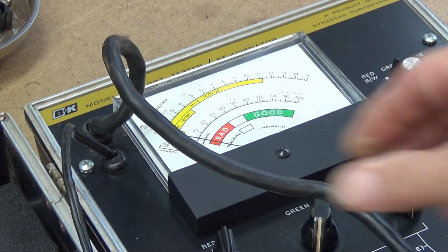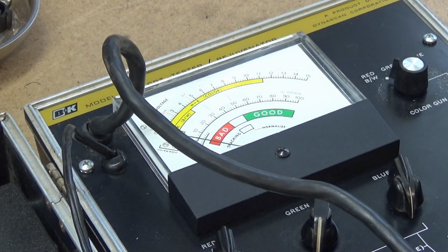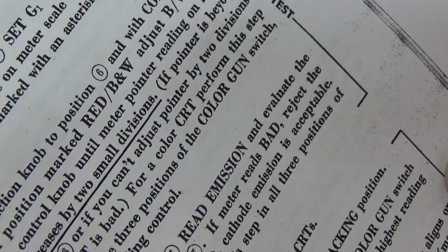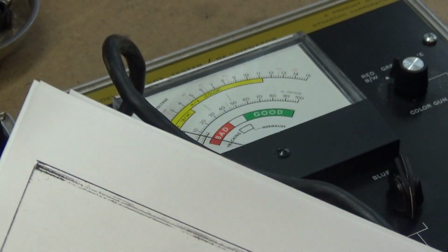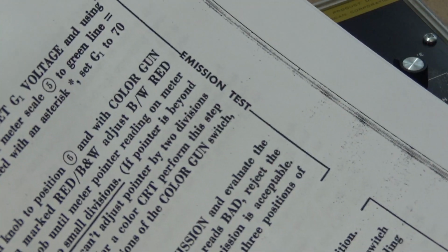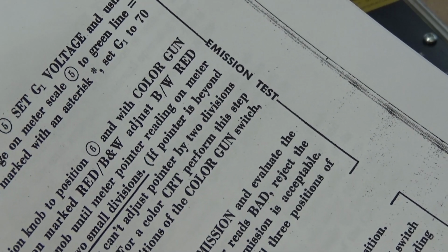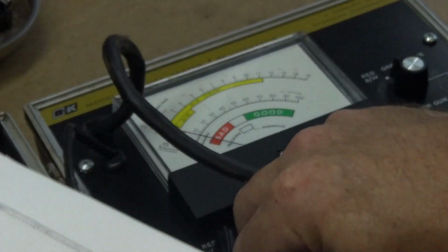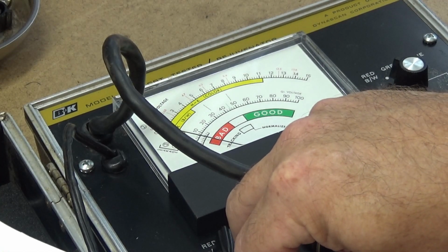This is G1 leakage. G1 voltage, let's go to that. Set large function knob to G1 voltage, position 5. Now we want to use meter scale 5 to the green line, approximately 145 volts.